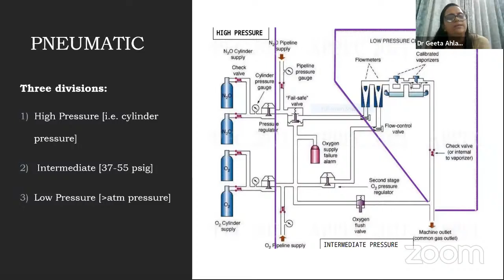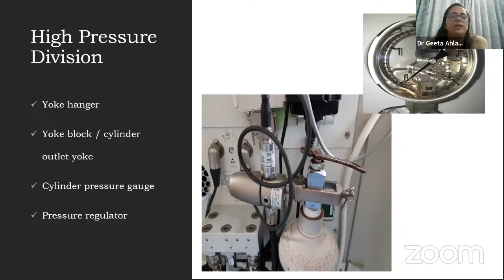So the yoke assembly is where the cylinder is hung, and it is kept straight by this yoke. It is because of the yoke that the cylinder can be connected well to the machine. It is of equal importance. Then there is a cylinder pressure gauge, which tells you what is inside your cylinder, how much gas is left at each and every moment, and the pressure regulator valve, which allows you to use the pressure. Yoke hanger, as is visible to us, as we are well aware.